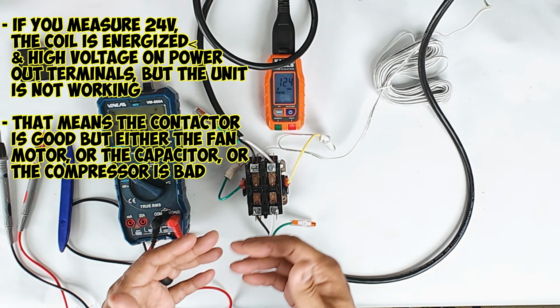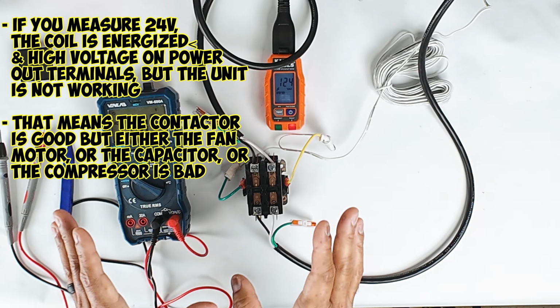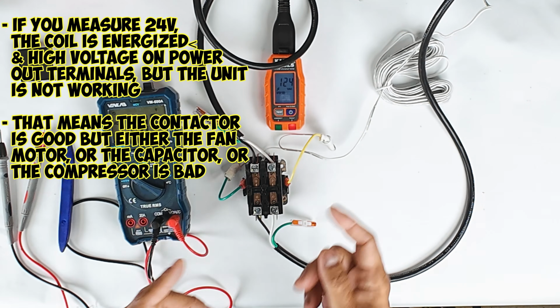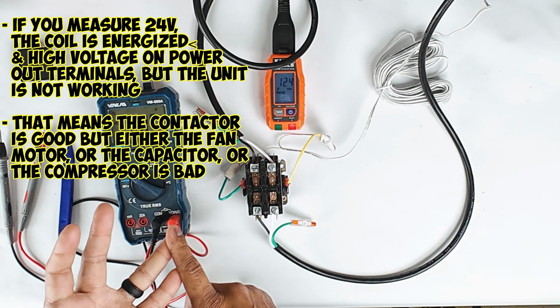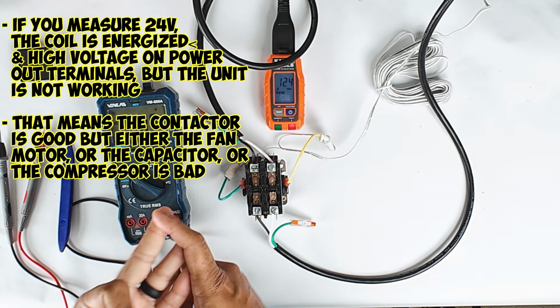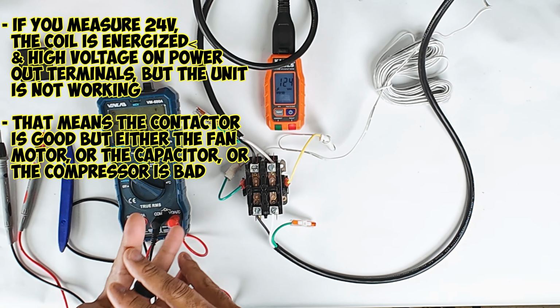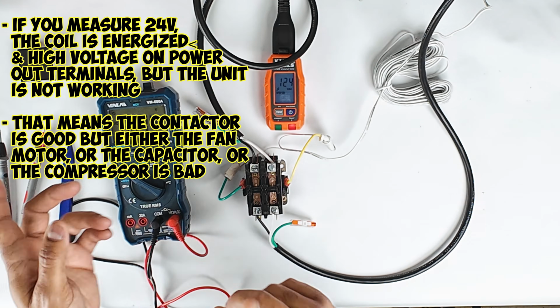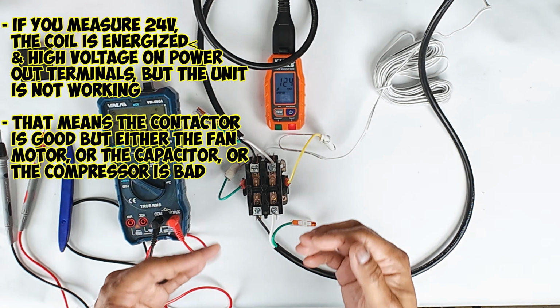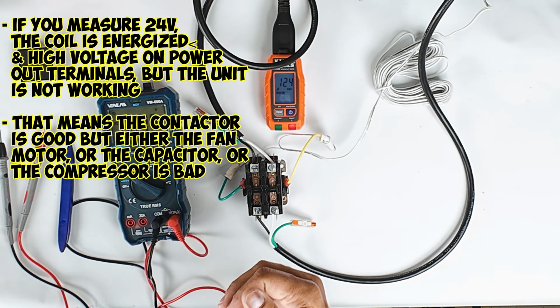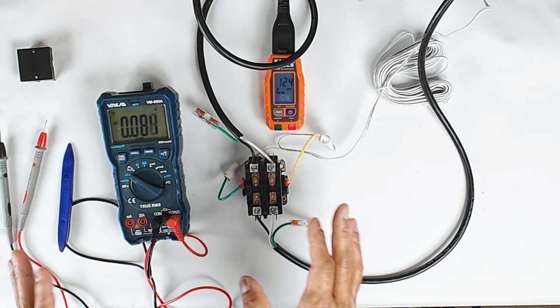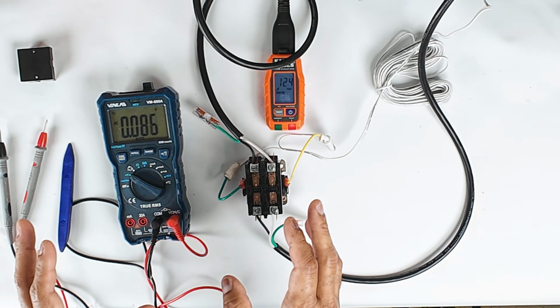If you have voltage and the unit is not running, then the problem is either with your capacitor, your fan motor, or your compressor. And I have videos for those as well. So if you want to, you can check them out to see how to troubleshoot those if you've gotten past this stage. Once you have run through all the steps and all the troubleshooting procedures, you are done.